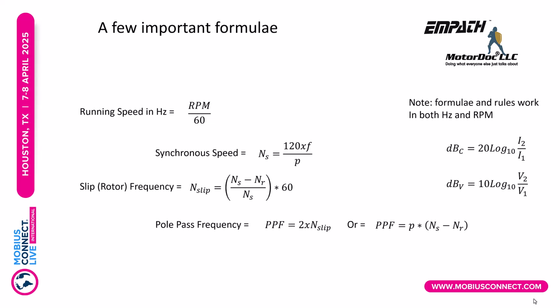is the actual rotating speed of the magnetic field in the stator. That is 120, which is a constant, times the applied frequency divided by the number of poles. It's always in groups of 2, so 2, 4, 6, 8, 10. So if I have a 60 hertz machine, that's 7,200 divided by 2, which is 3,600, 1,800, 1,200, etc. Slip is what we actually get because the motor can never keep up with that turning field. It always has to fall behind a little bit so that the magnetic fields cut across the rotor bars in order to develop torque. And that actually varies based upon the load. So the heavier the load, the more slip occurs.